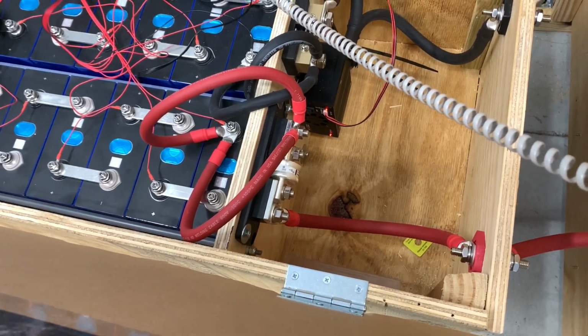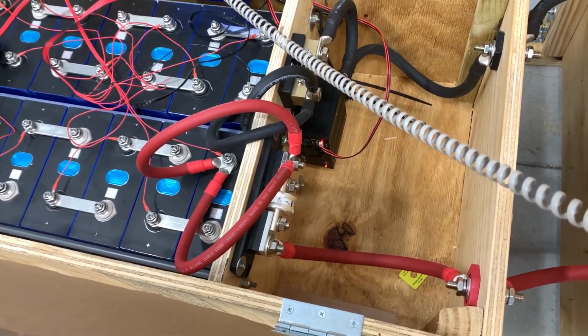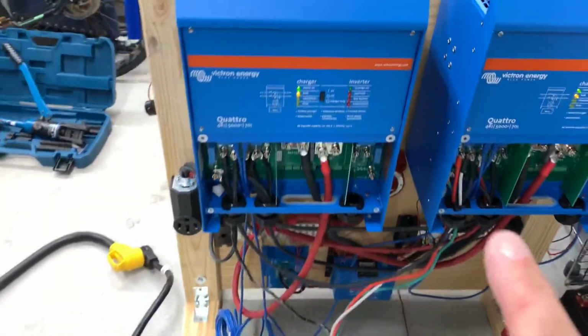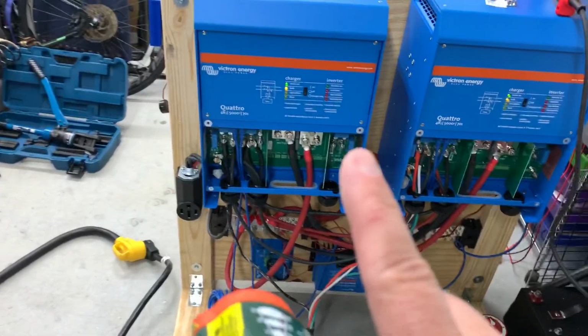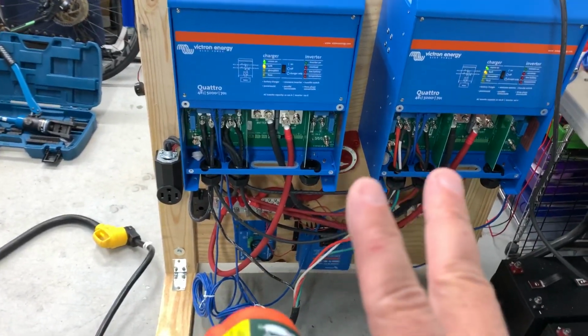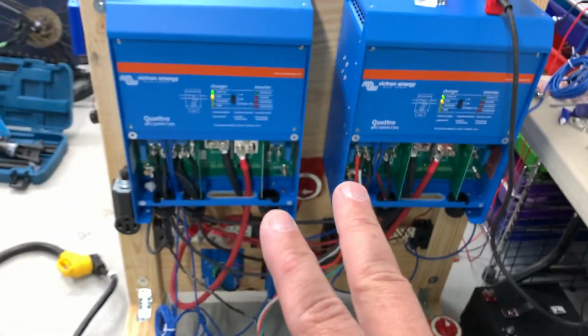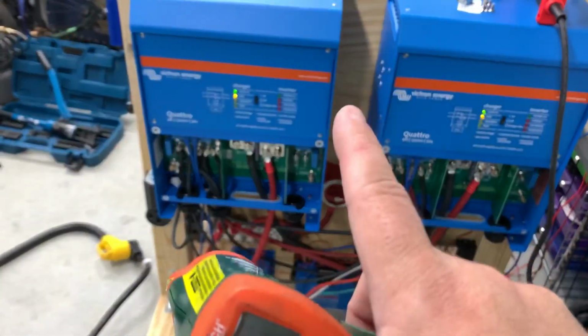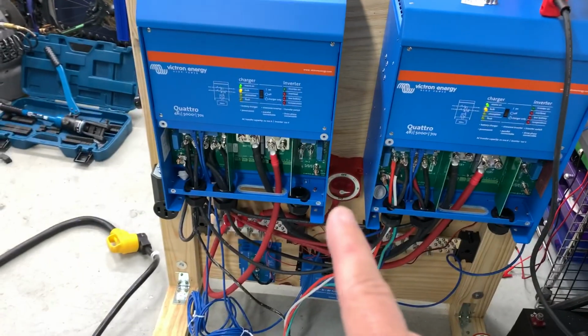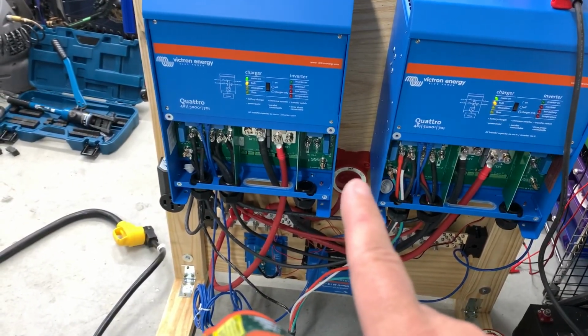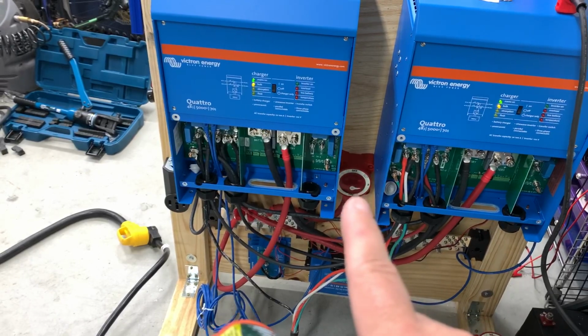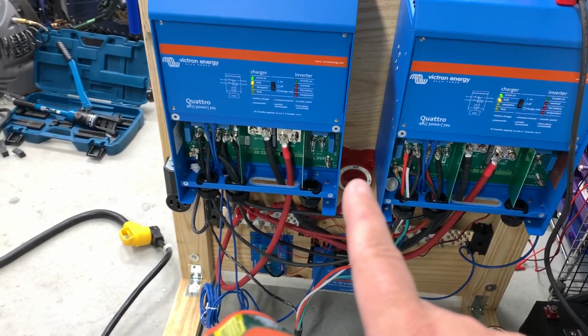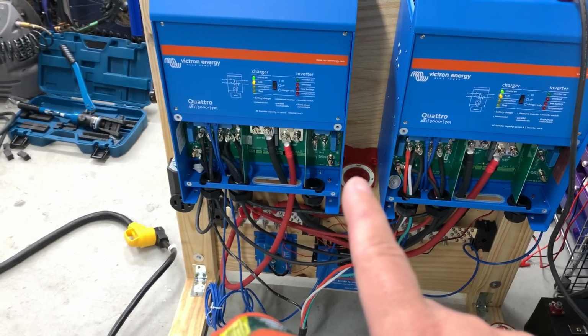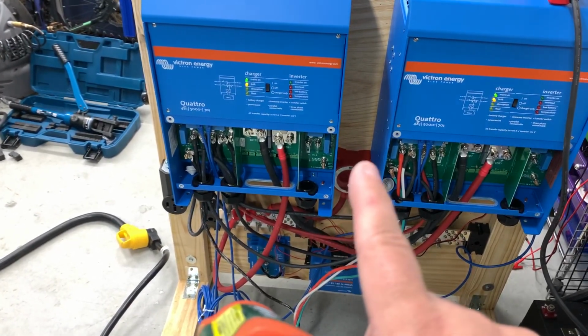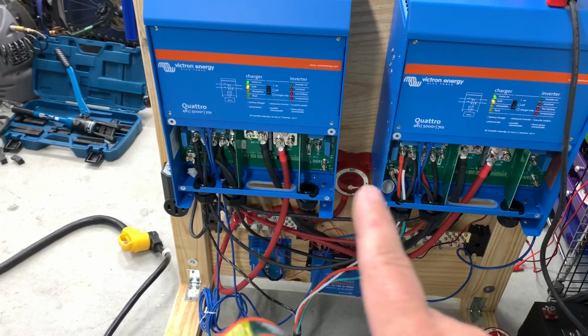I don't know if that has to do with its capacitor pre-charge circuit, which is really important for inverters, especially of this size. If you just connect the DC power to these for the first time, you get a huge arc, especially at these voltages. So what's been happening is even with the contactor off, when I turn on the battery switch, I get a huge arc in that switch, which is not good. I'm degrading that switch every time I do this. It's also concerning, if the contactor shuts off, is it still going to pass power?